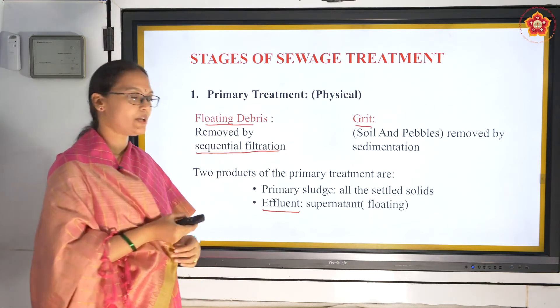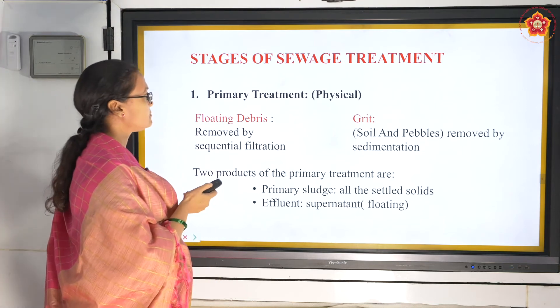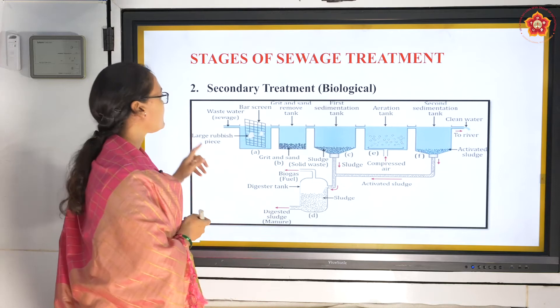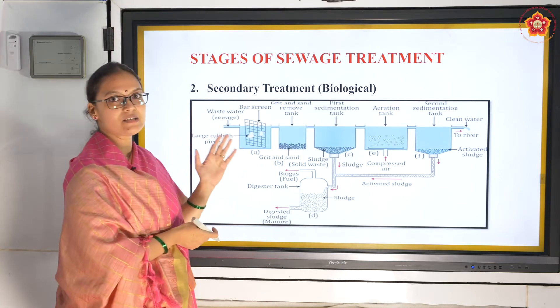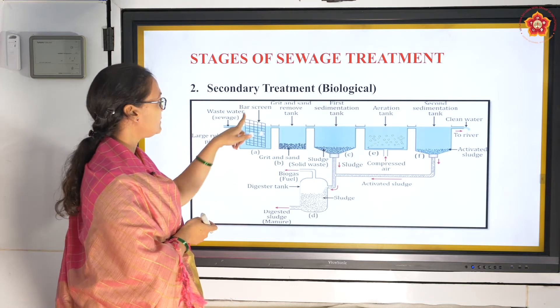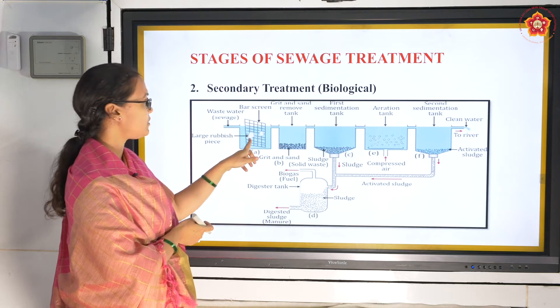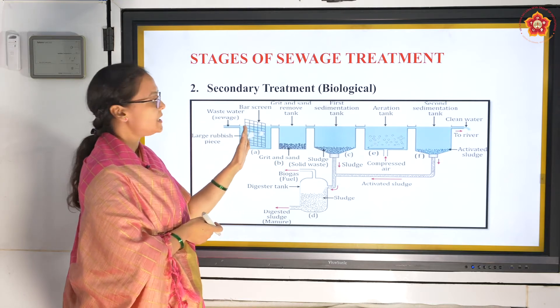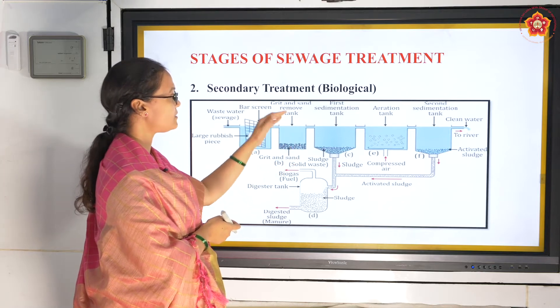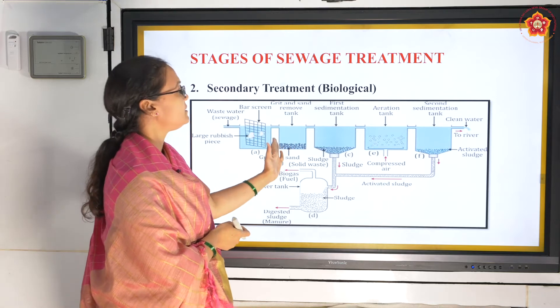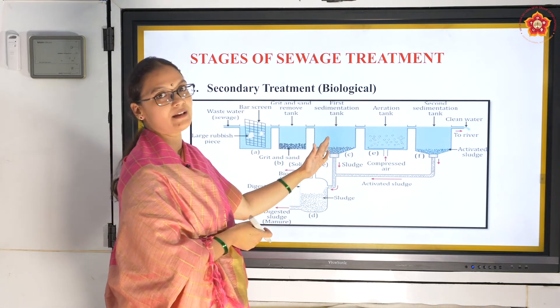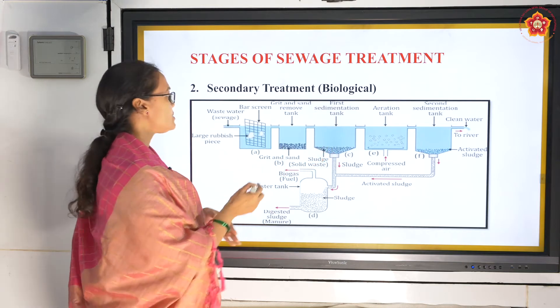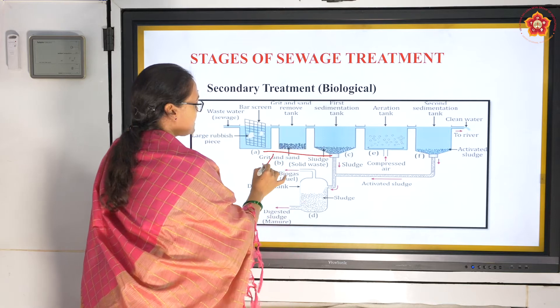This is how a sewage treatment plant looks like. As I mentioned, the first stage is the physical stage - wastewater enters and a bar screen, which is the filter, stops all the big floating debris like large rubbish pieces and plastic bottles. Next the water is taken into a settling tank where grit is removed by sedimentation, then into the first sedimentation tank. From A to C, this part is the physical part.